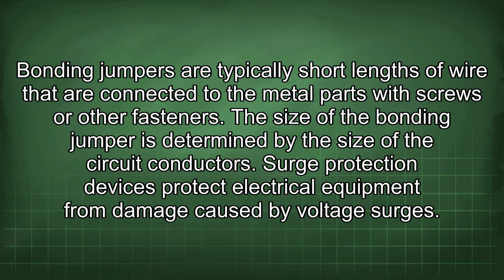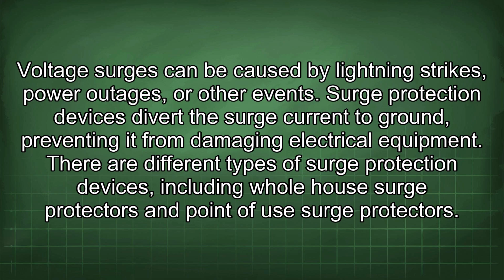Surge protection devices protect electrical equipment from damage caused by voltage surges. Voltage surges can be caused by lightning strikes, power outages, or other events. Surge protection devices divert the surge current to ground, preventing it from damaging electrical equipment. There are different types of surge protection devices, including whole-house surge protectors and point-of-use surge protectors.